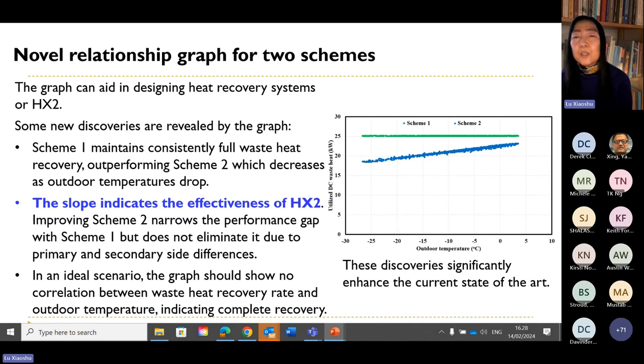We also developed a new relationship graph based on the two schemes, because a linear correlation can be found among the waste heat reuse rate, outdoor temperature, as well as space heating supply temperature. Therefore, this graph can be used to aid in designing the heat recovery system or HX2. And there are some new discoveries from the graph. First, scheme one keeps constantly complete waste heat recovery, outperforming scheme two. Scheme two is this blue line.